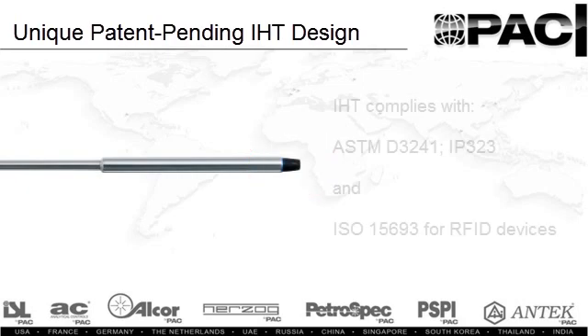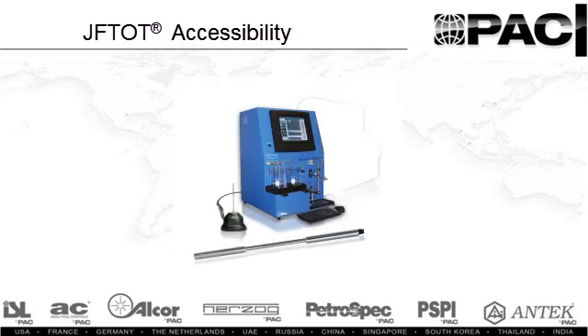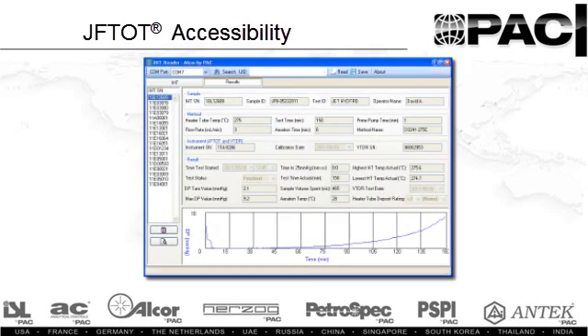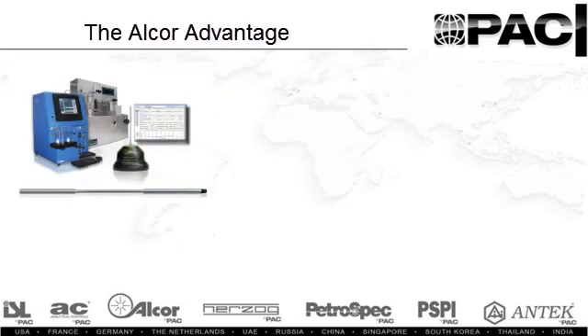The IHT meets ASTM D3241 and IP323 standards and adheres to ISO 15693 standards for RFID devices. When docked with the IHT Reader-Writer, the Intelligent Heater Tube is immediately accessible via USB from all JFTOT 3 and most JFTOT 2 instruments. Results are written once and can be read any number of times from the built-in software of the JFTOT 3 or the companion PC associated with the JFTOT 2.